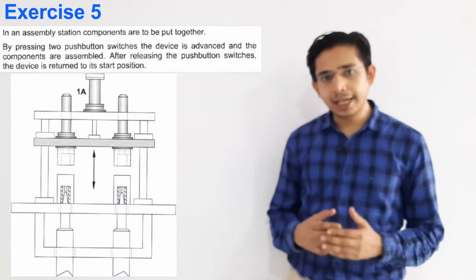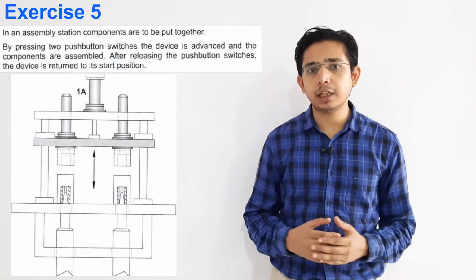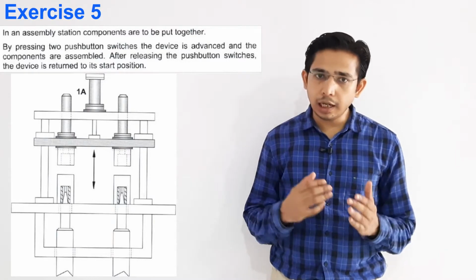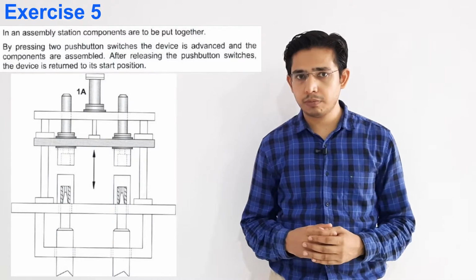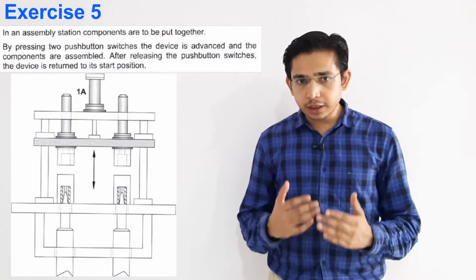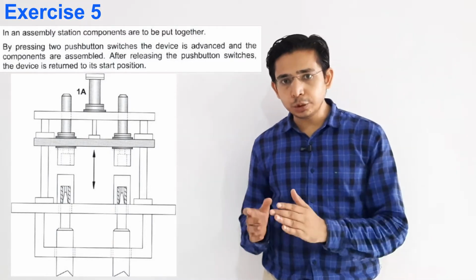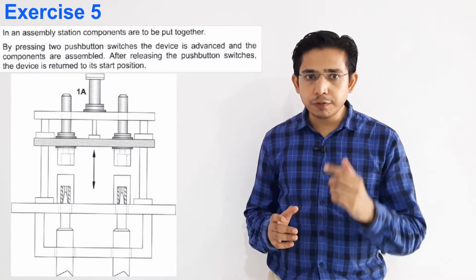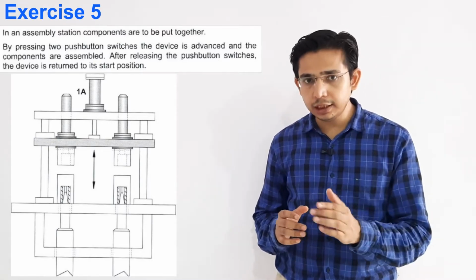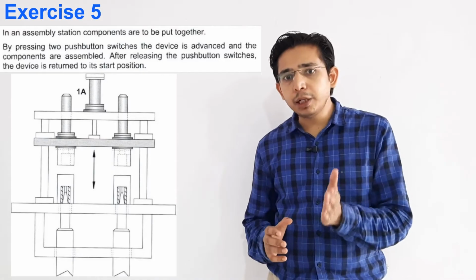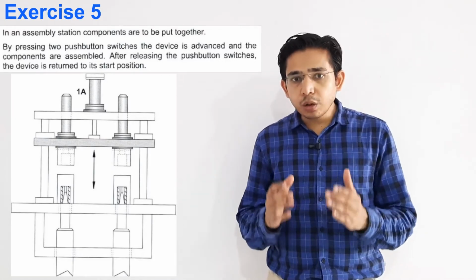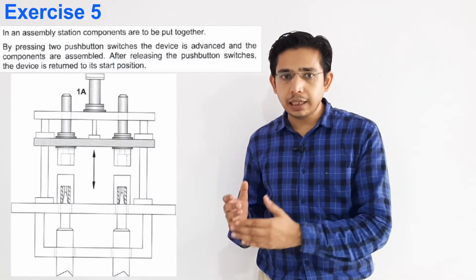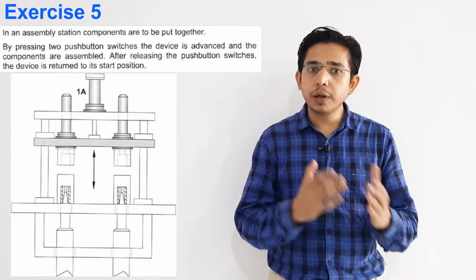This problem has to be solved with the help of pneumatic technology, and along with it we also have to use electronic technology. By pressing the push button switches S1 and S2, the electric circuit for the solenoid coil 1Y is closed and the 5x2 way solenoid valve is reversed. The piston rod of the double acting cylinder advances to the forward end position.